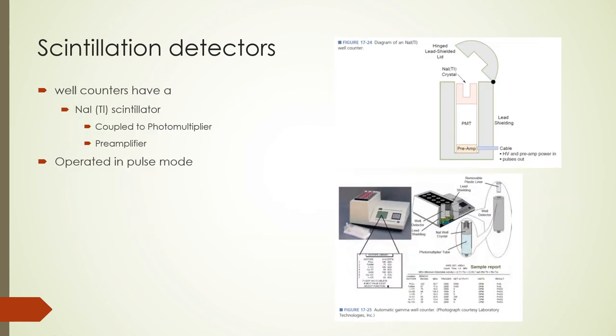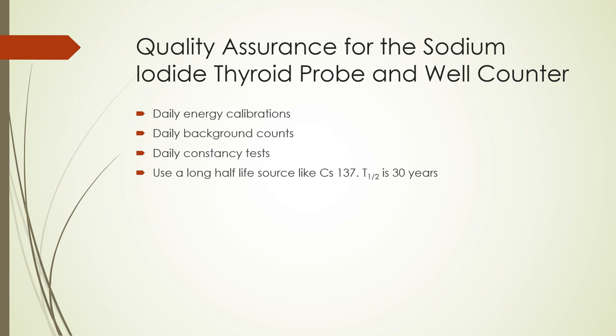The next instrument using a scintillator is the well counter. A well counter is commonly used to assay wipe test samples to detect radioactive contamination. It can also be used for clinical tests and radio-immunoassays. Well counters consist of a cylindrical sodium iodide crystal with a hole in the crystal for insertion of a sample. This configuration is geometrically efficient and allows the assay of samples as small as one nanocurie. The crystal is coupled to a photomultiplier tube and a pre-amplifier. The entire setup is placed in a thick lead shield. Both thyroid probes and well counters should have daily energy calibrations performed, along with daily background counts and daily constancy tests using a long half-life source like cesium-137.